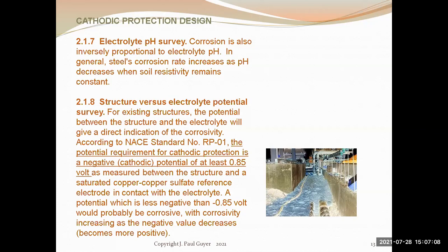The structure is the thing that you are protecting. It's the cathode, and the electrolyte is the soil. An important number to bear in mind is minus 0.85 volts. In other words, and this is according to an industry standard, NACE standard RP0169, National Association of Corrosion Engineers.